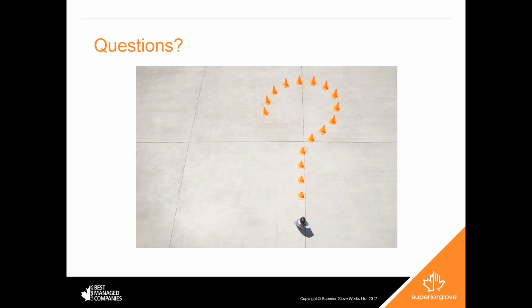Just in a more general idea, what are really the best ways to prevent an arc flash? Yeah, so along with the lockout tagouts, the de-energize, and the things that Robert had just mentioned, your arc flashes can be caused by equipment failure or loose connections. So you want to make sure that your machinery is being well maintained. Again, human error is a huge cause of this, so regular analysis of your equipment, work practices, and safety training are the things that you want to look at before you look into the PPE, because PPE is your last resort in this type of situation.